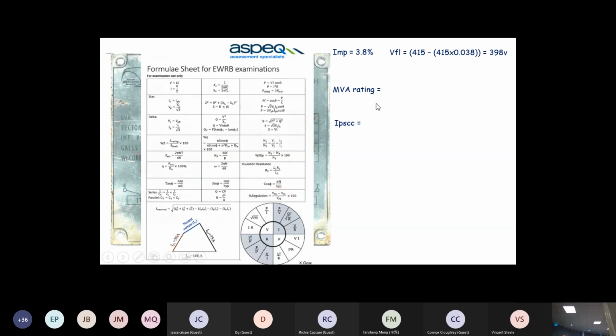Right. What's meant by the term MVA rating? Firstly, do you all agree this is a 200 kVA transformer? You all agree? See that? 200 kVA. Now, what does kVA stand for? Kilovolt amps. Right. Anyone with a calculator? Do the following. Say √3. Yes, maximum volt amps. That's right. So anyone who's got a calculator, go for me and say √3 times 415 times 278.